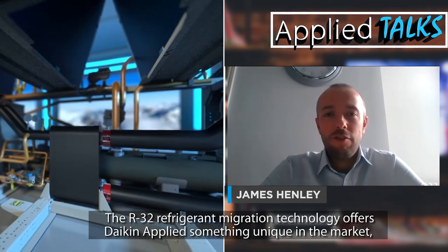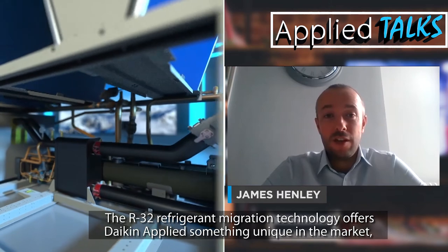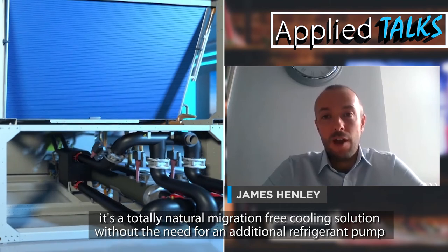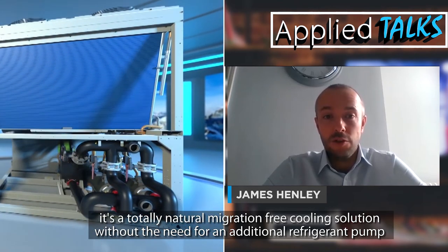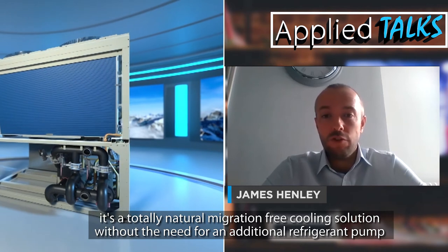The R32 refrigerant migration technology offers Daikin Applied something really unique in the market. It's a totally natural migration free cooling solution without the need for an additional refrigerant pump or increased footprint. And with the two different free cooling levels, the light version starting free cooling from 4 degrees below your chilled water set point and giving up to 25% free cooling, or the full version starting from just 1 degree below your chilled water set point and up to 80% free cooling capacity.